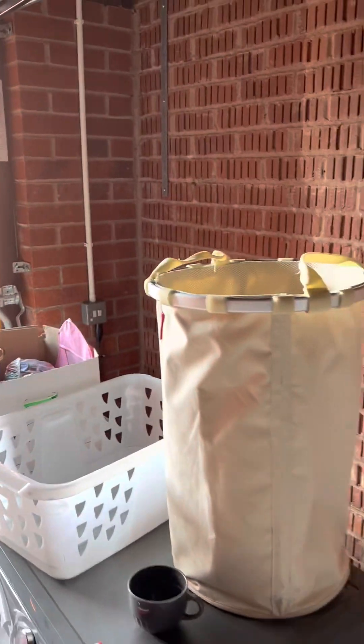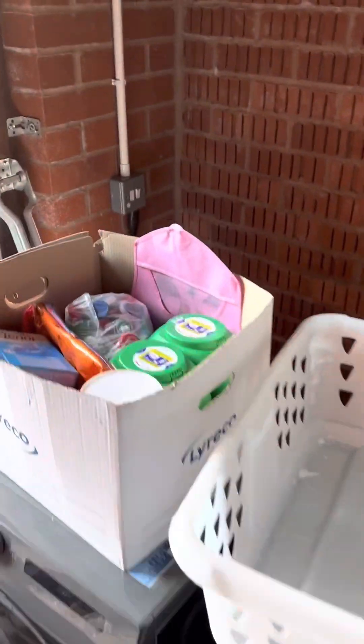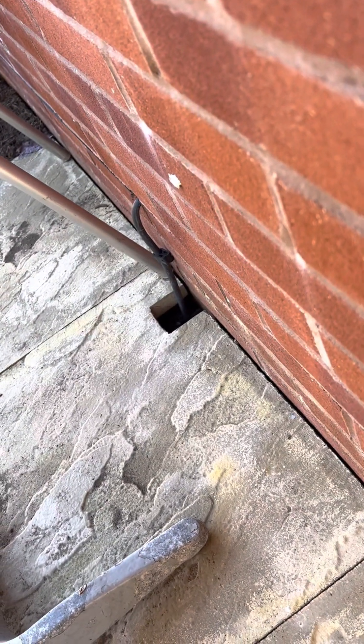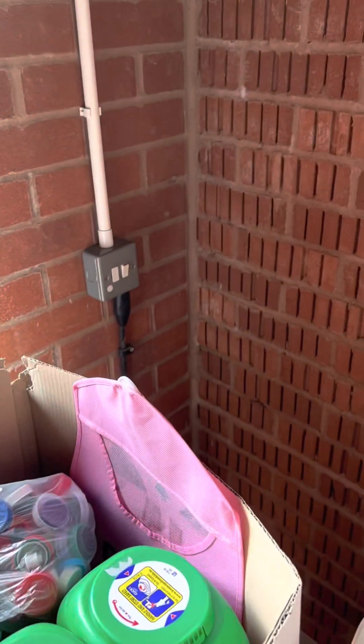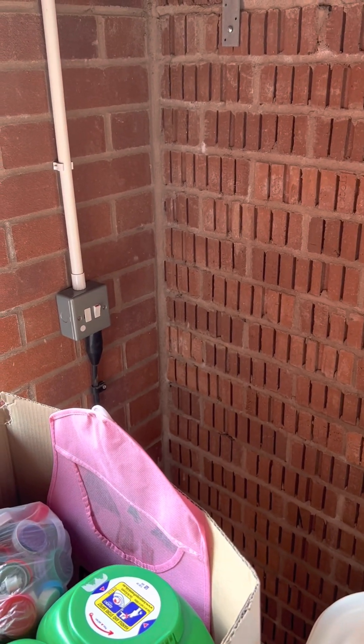I've got a job to install an extra socket in this new build. It looks like a 1.5mm armored cable - there's a terrible bit of cutting out there by the patio. Round to a box on the back of the house, and I cannot find a fused connection unit anywhere in the house. The homeowner isn't aware of one either - I cannot find a fused connection unit for the garage.